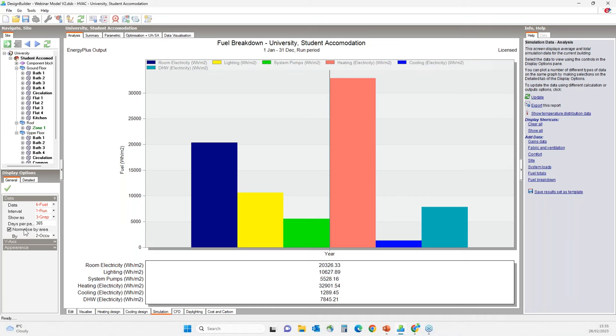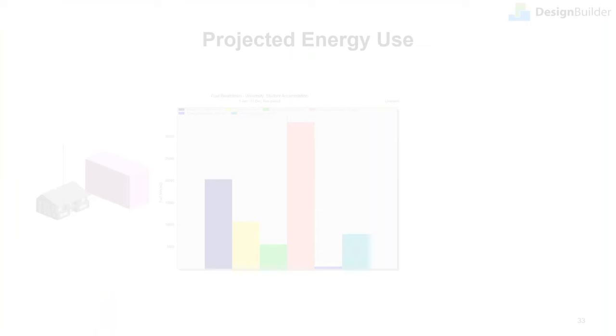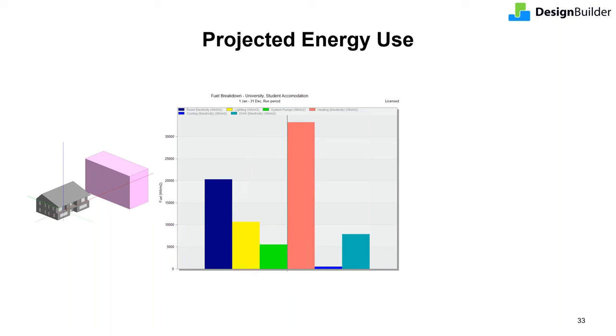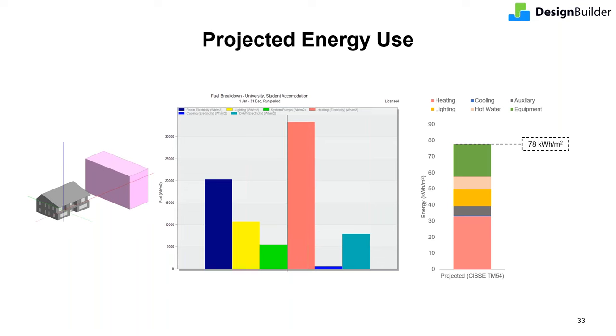This is the projected energy use based on realistic operating conditions and represents the baseline energy use. The energy use projection calculated in accordance with TM54 guidelines with building-specific inputs results in a total projection of 78 kWh per meter square per annum. This projection accounts for all anticipated energy uses in the building rather than just the regulatory loads or central plant equipment, and therefore provides a holistic view of the building's performance.